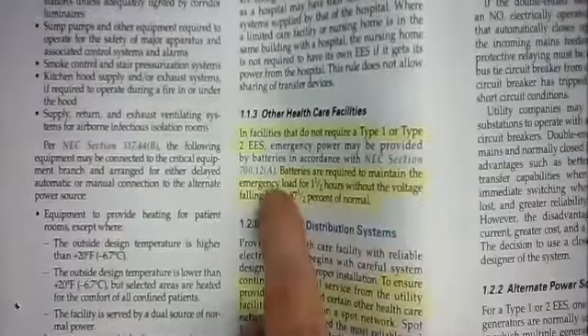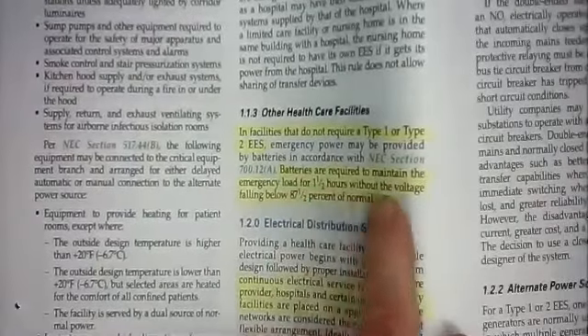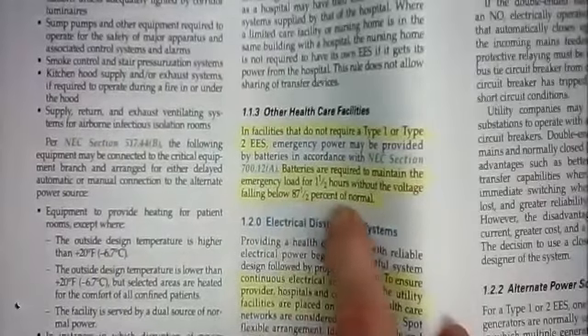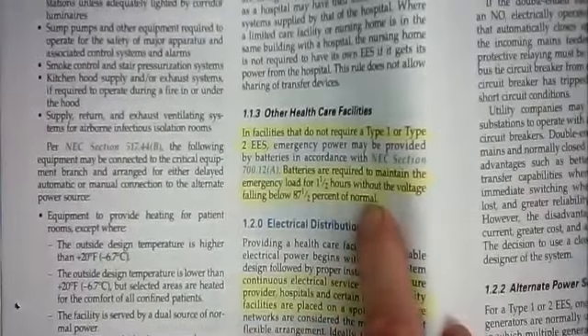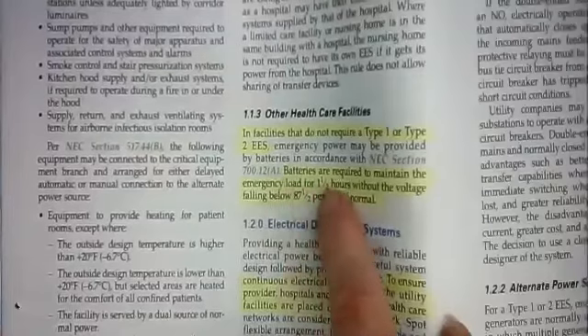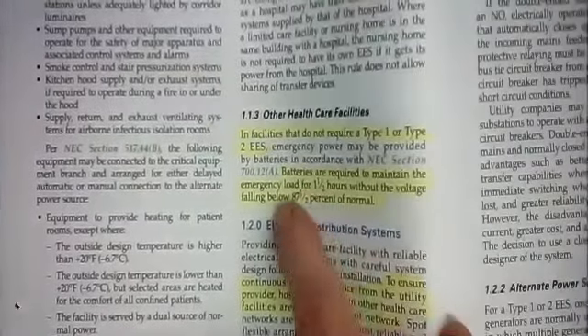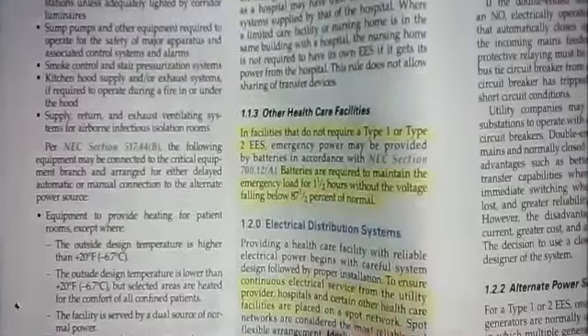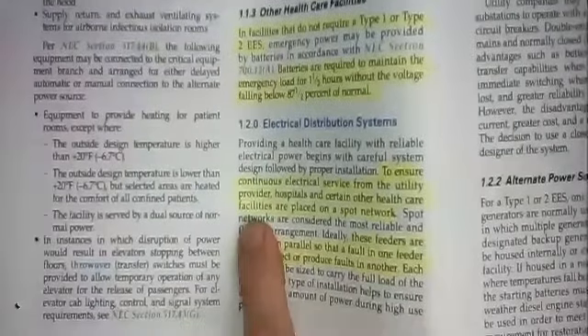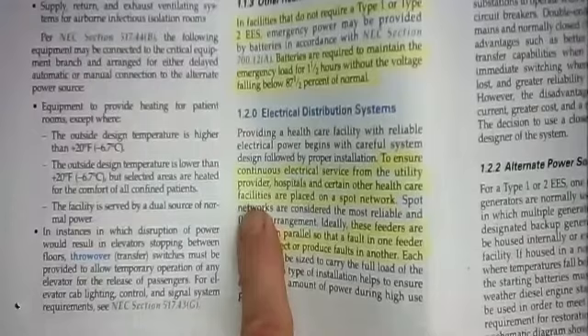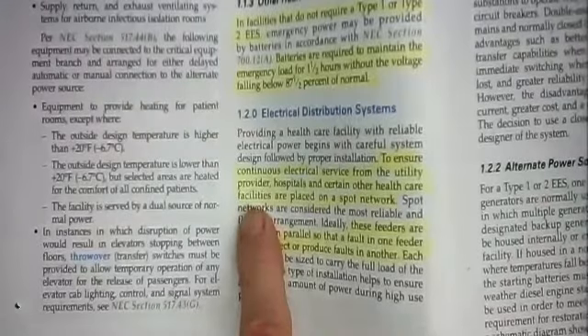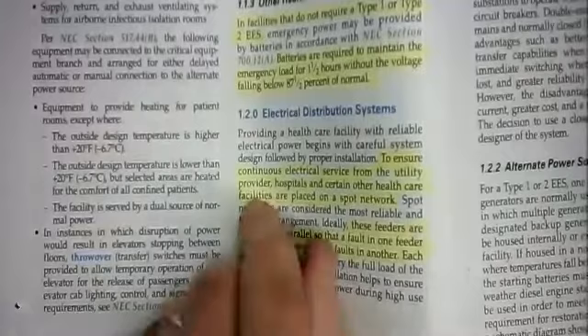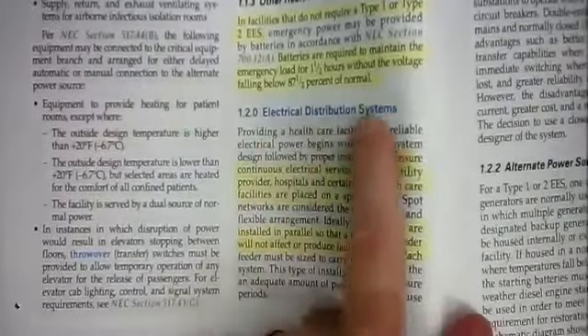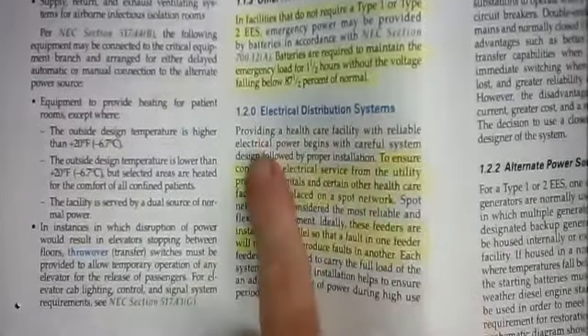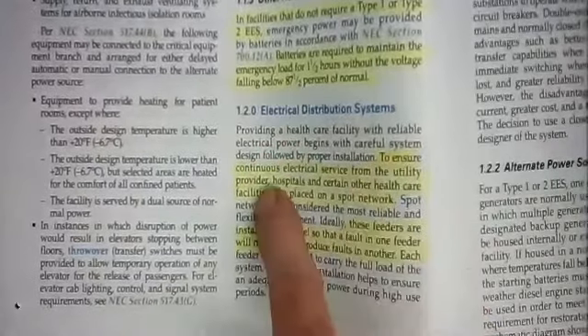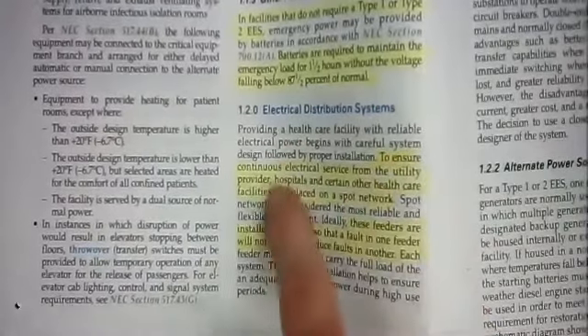Batteries are required to maintain emergency load for up to an hour and a half without the voltage falling below 87.5% of normal. Okay? So batteries are required to maintain the emergency load for an hour and a half without the voltage falling below 87.5% of normal. And that's again in a facility that does not require either a type 1 essential electrical system or a type 2 essential electrical system. Electrical distribution systems on page 6, right-hand column, very bottom of the page, to ensure continuous electrical service from the utility provider.